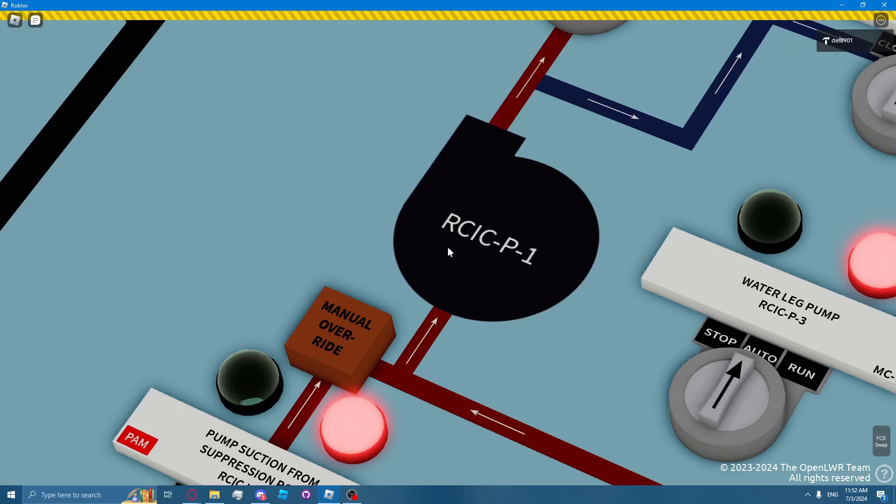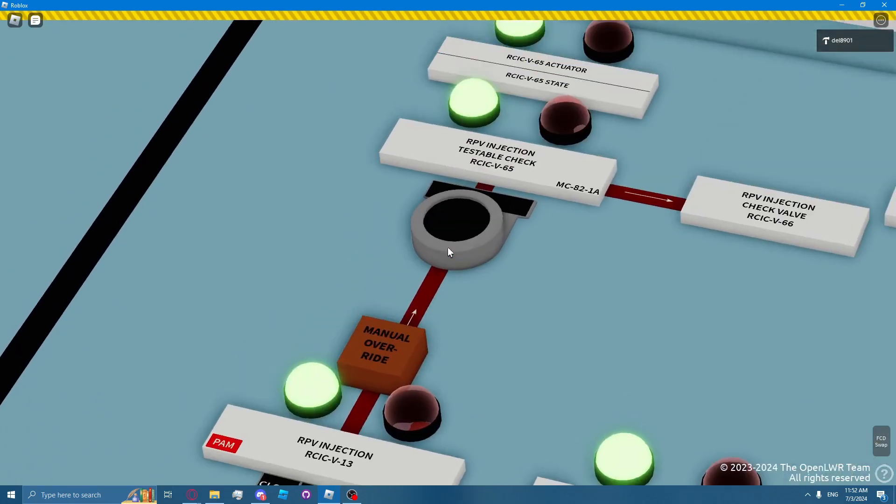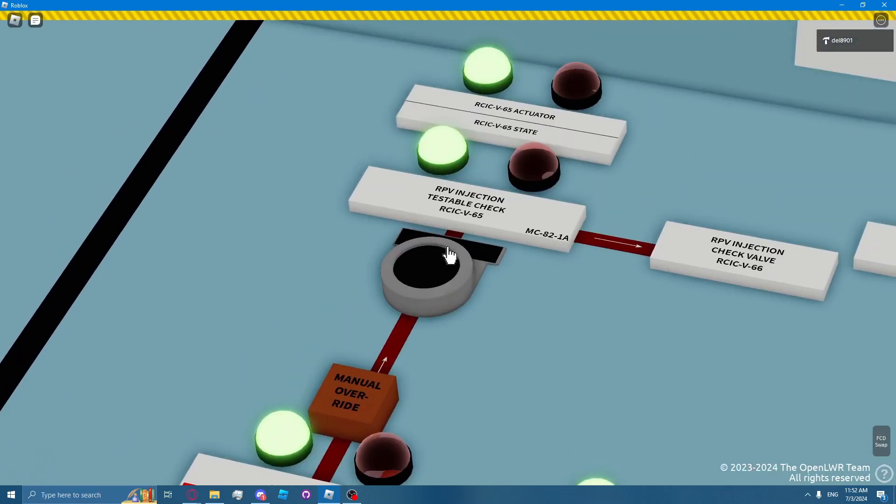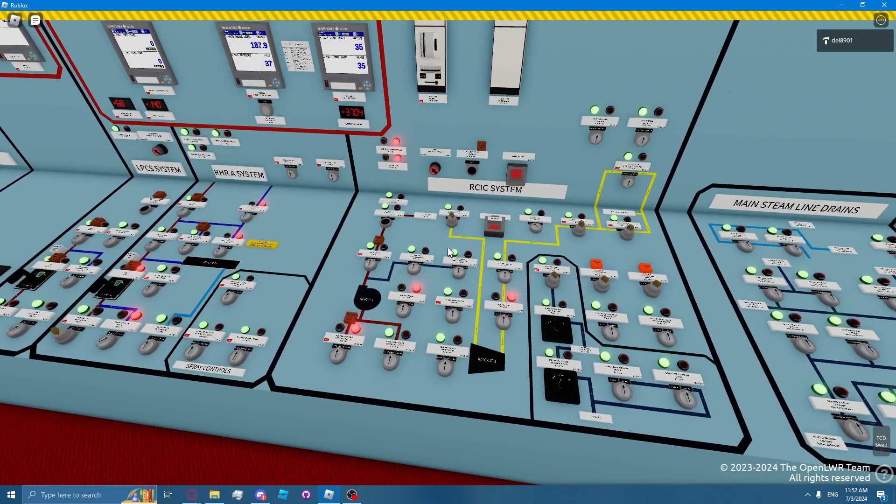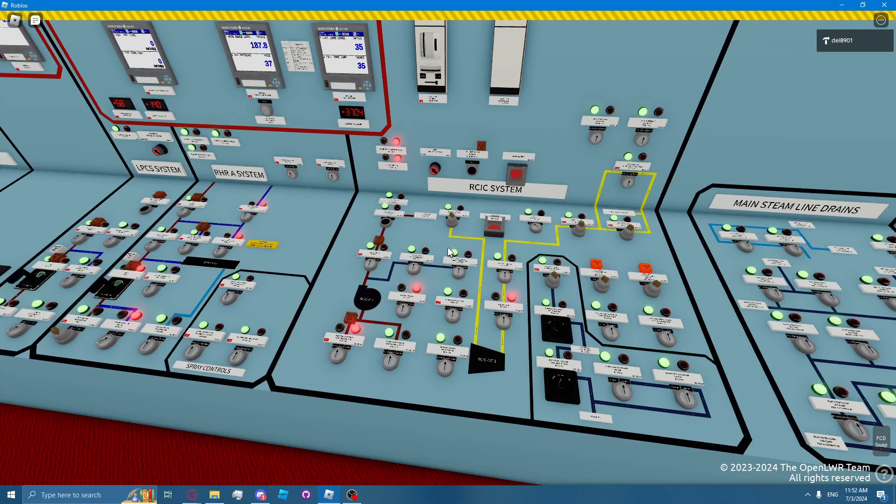The RCIC pump discharges through the system flow element, then the discharge valve, then the air-operated check valve. RCIC injects through the reactor through the RHR head spray line. This allows RCIC to condense the reactor head steam, which adds additional system flow rate and lowers reactor pressure.